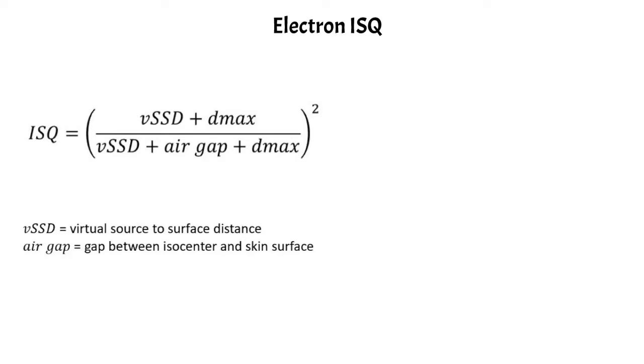The vSSD is your virtual source to surface distance, and then your air gap is the gap between the isocenter and the skin surface. So you use the virtual SSD in your inverse square correction rather than the actual SSD.